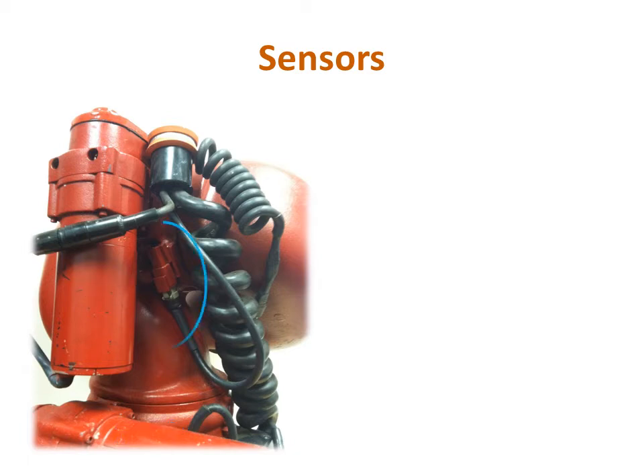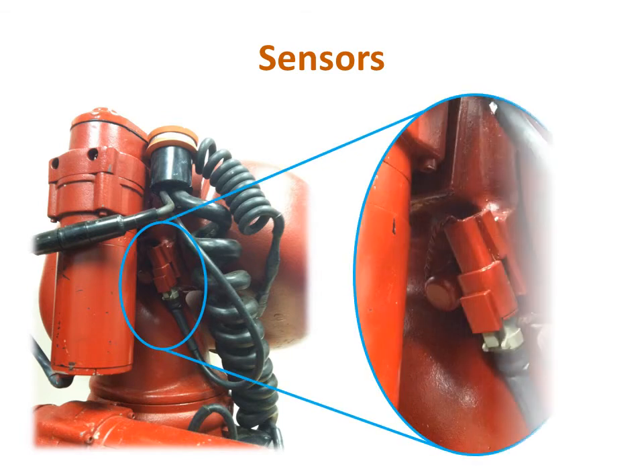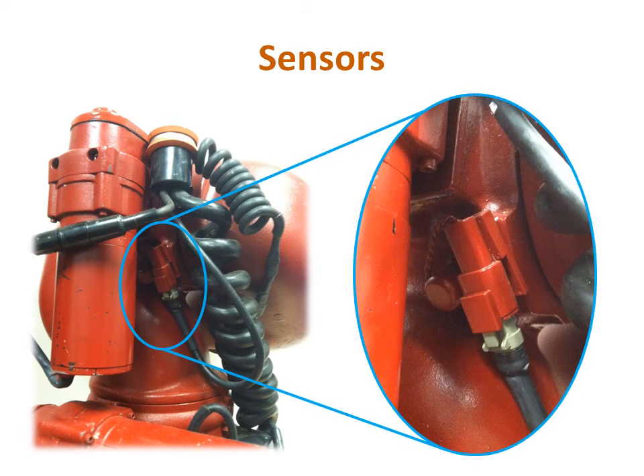Now let's zoom in a little bit and examine the sensor assembly itself. The most visible part of the sensor assembly, which the first arrow points to, is not actually the sensor. It is the socket that the wiring harness plugs into. The second arrow points to the sensor housing that screws into the monitor. Both the elevation and rotation sensors are identical and come packaged together if replacement sensors are ordered. The magnets that these sensors react to are internal to the monitor and are not adjustable. We will discuss the sensors further in the troubleshooting section.